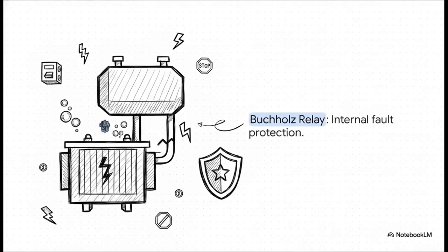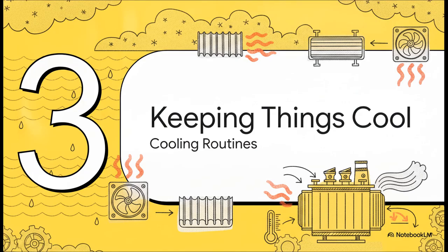For any unit above 1 MVA, this mechanical relay is your very first line of defense. It literally catches gas bubbles produced by internal electrical faults. If things start getting out of hand, it connects straight to the circuit breaker's trip coil and shuts the entire system down way before a catastrophic failure can happen. Let's shift gears to Section 3, Keeping Things Cool.